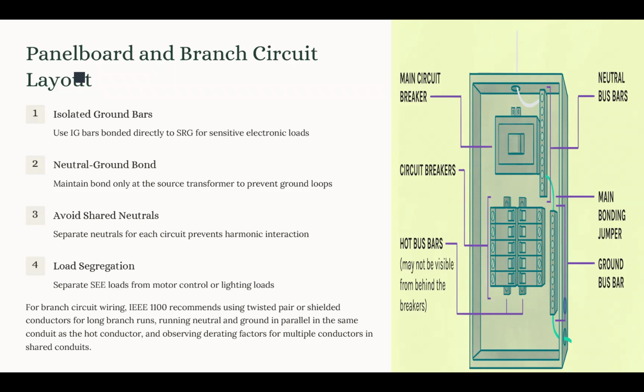Now we also have to make sure that we maintain the neutral to ground bond only at the source transformer. Why? Because we have to prevent parallel neutral ground paths. These could cause circulating ground currents or introduce common mode noise. Basically, if we don't do that, bonding the neutral to the ground at sub panels could create multiple current return paths, which induce ground loop voltages.